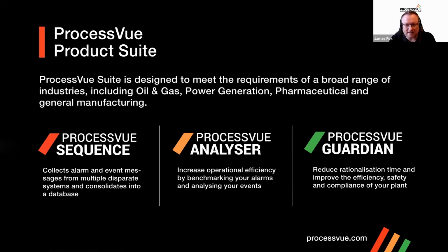We've then got the ProcessVue Analyzer, which is our analytics package. It allows users to identify nuisance alarms such as chattering, fleeting alarms. It allows us to look at the stale alarms, the longest standing alarms. And it also allows users to benchmark their alarm systems against the alarm management standards and guidelines, such as the ISA 18.2 alarm management standard, the EEMUA 191 guidelines, and of course the IEC 62682 standard.